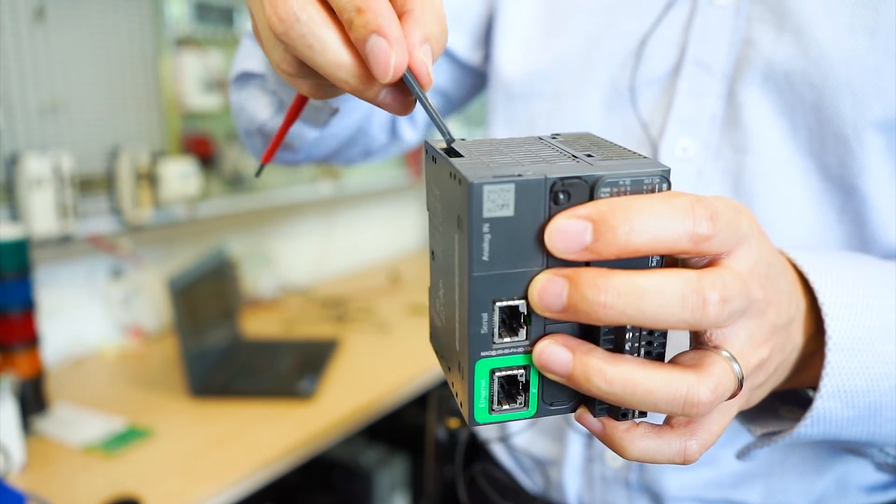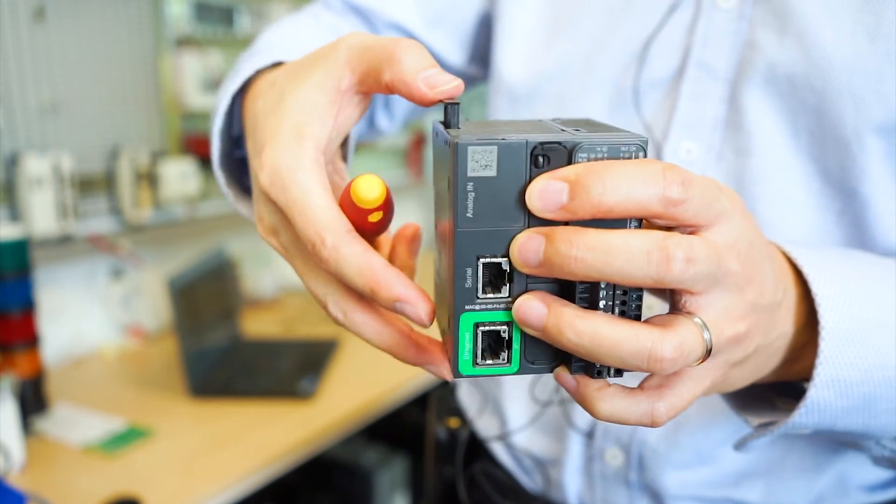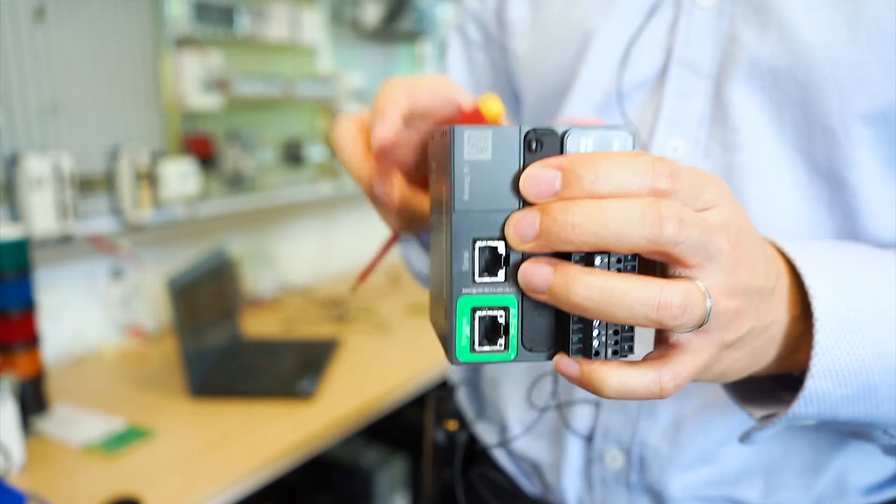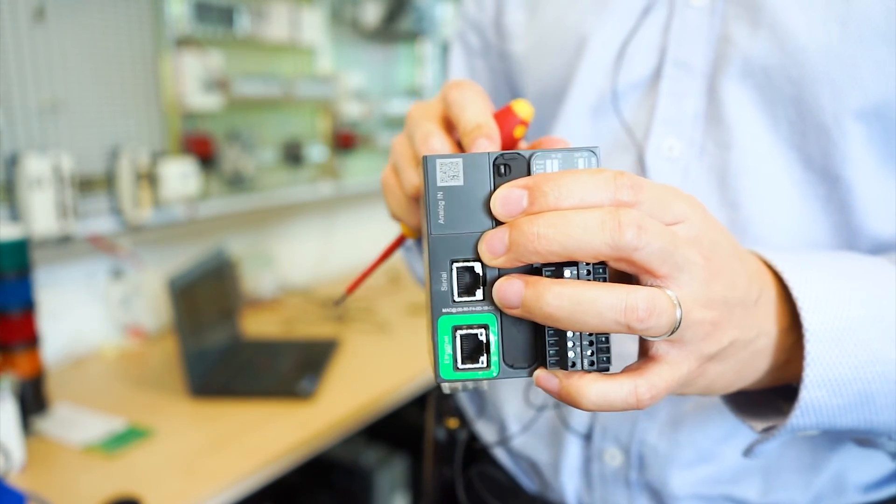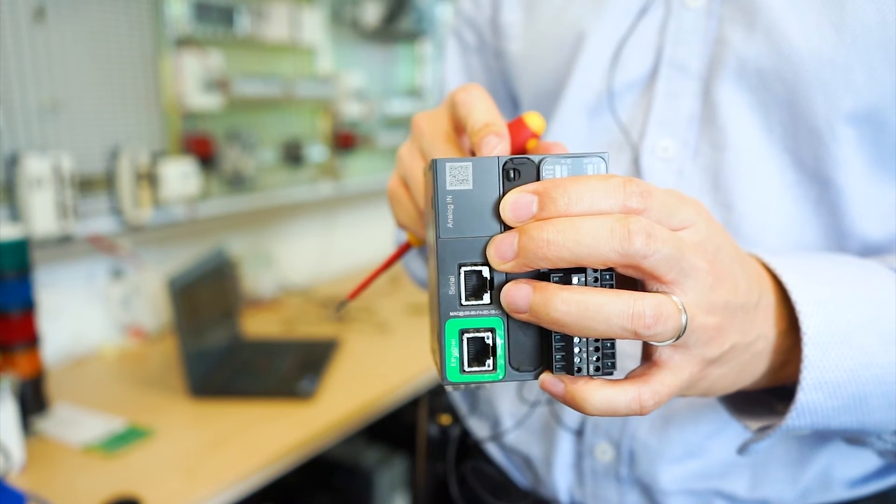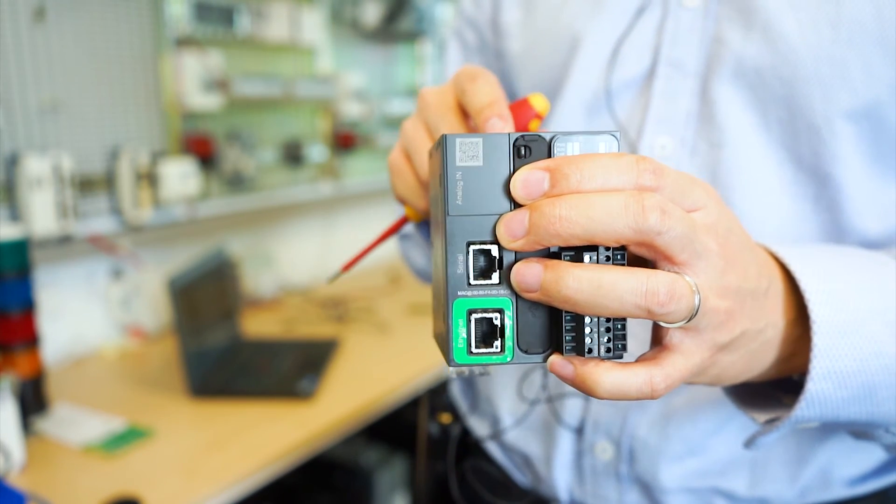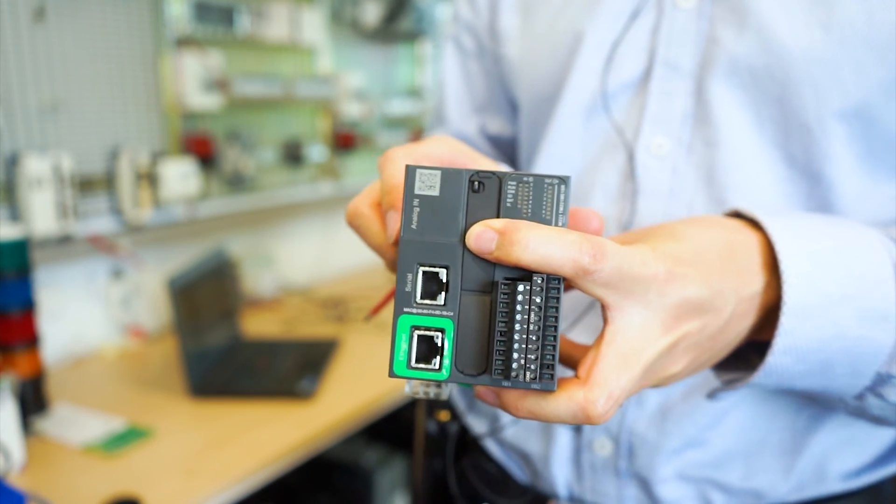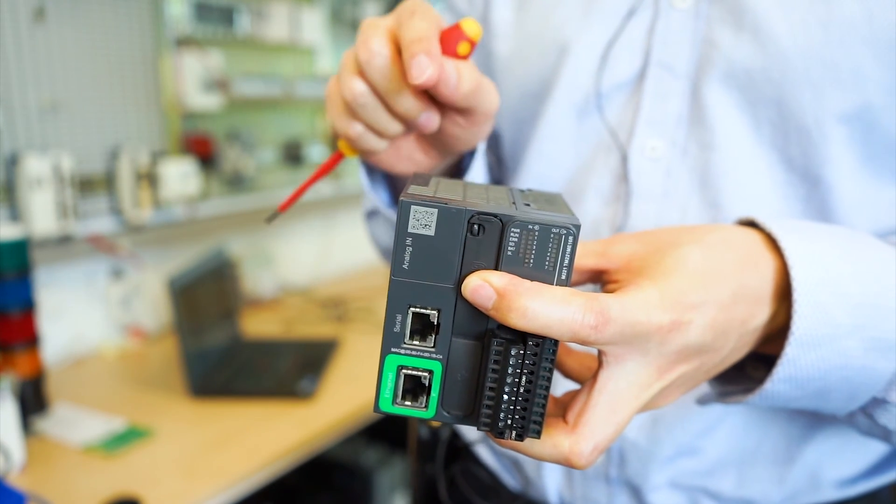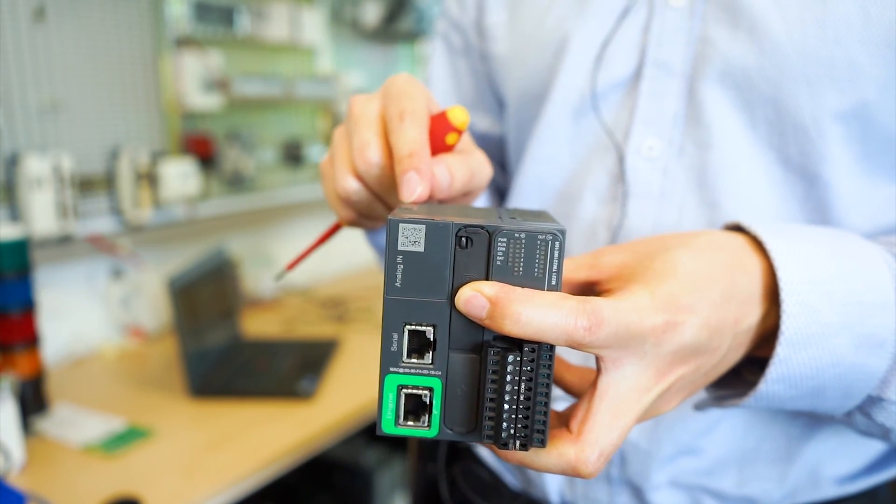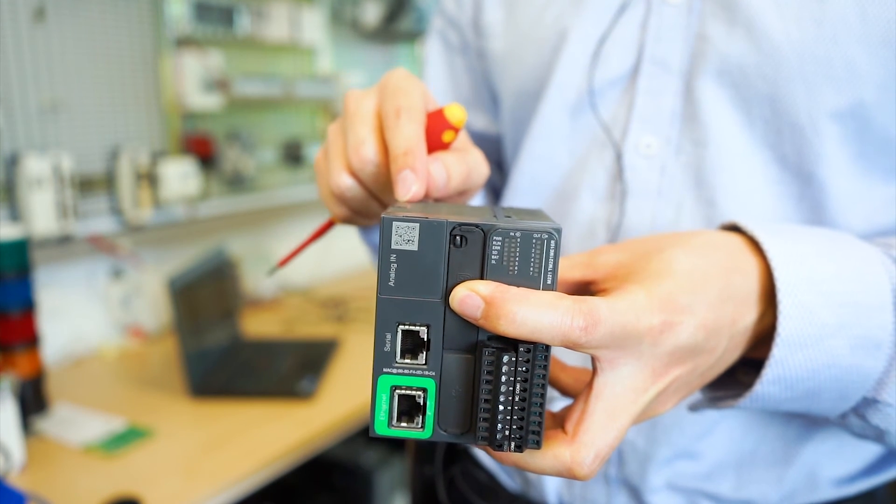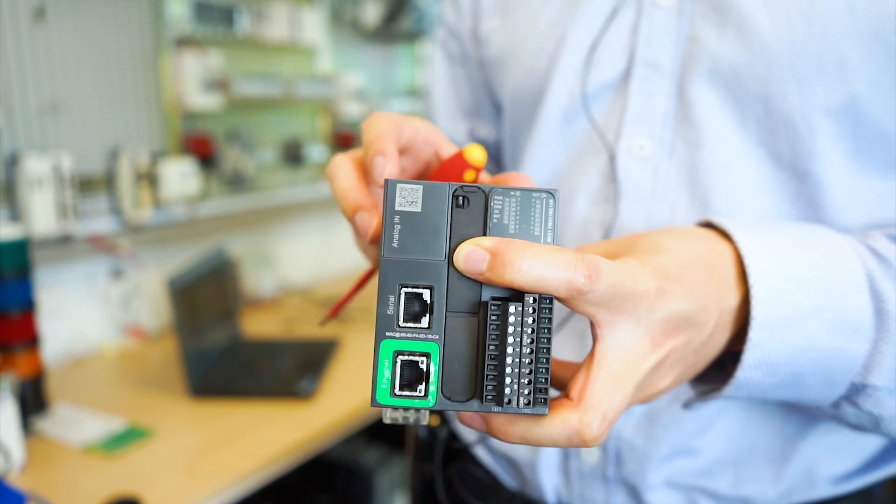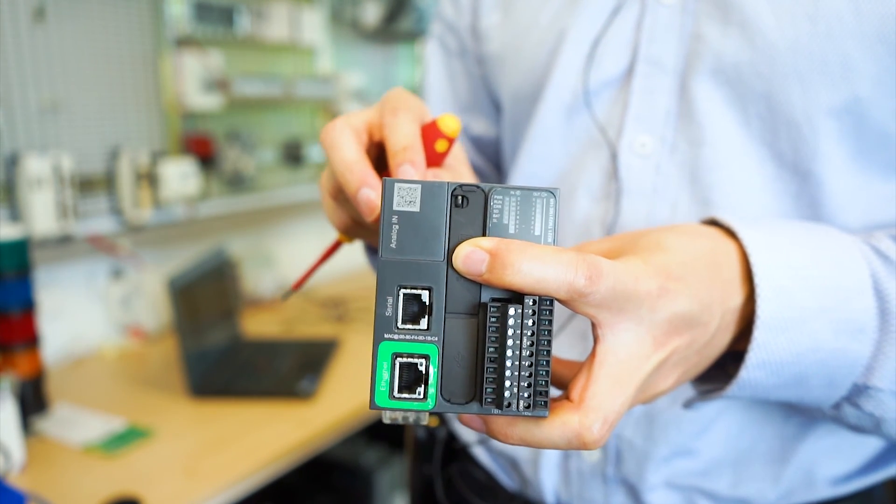The reason we have this battery here is because we have a real-time clock built into this controller. So we can use the battery to maintain the RTC and also to save all the data if there is a power interruption. The backup life for this battery is at least one year at 25 degrees maximum. If you run this controller in a higher temperature environment, the time will be reduced.